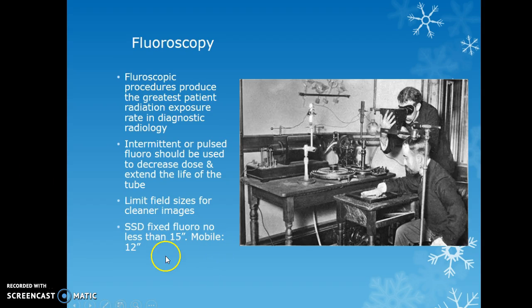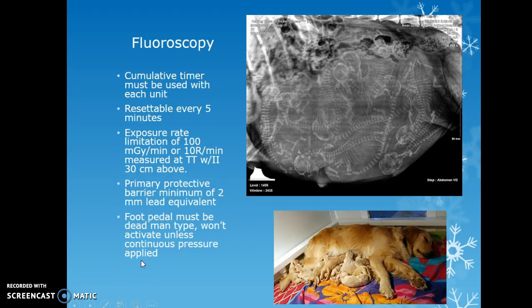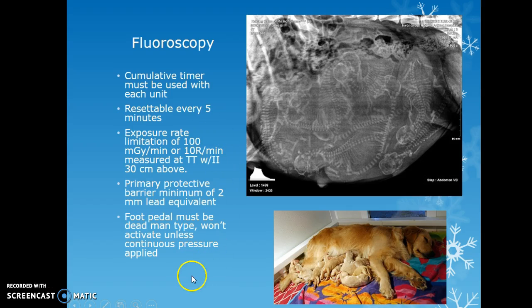For fluoroscopy, the SSD for fixed units is no less than 15 inches; for mobile units, the same 12 inches applies. A cumulative timer must be used, resettable every five minutes.